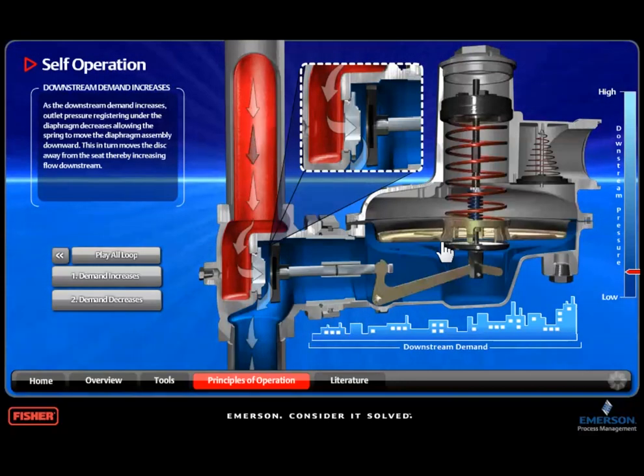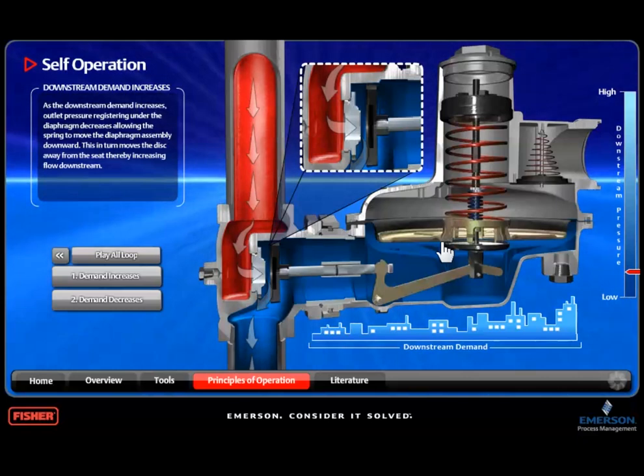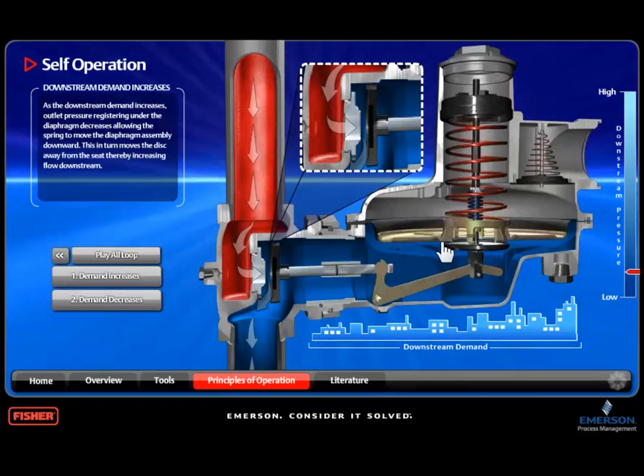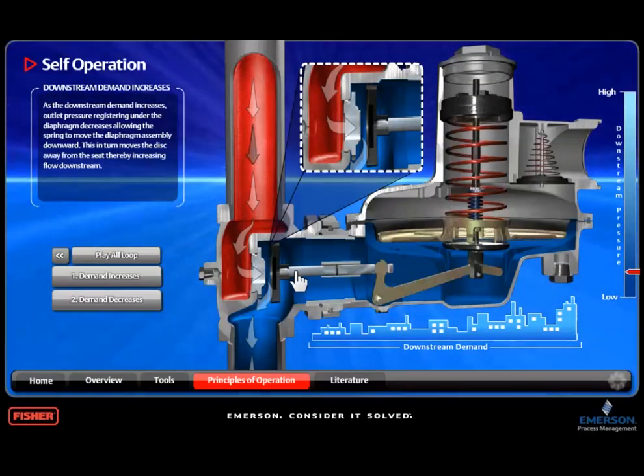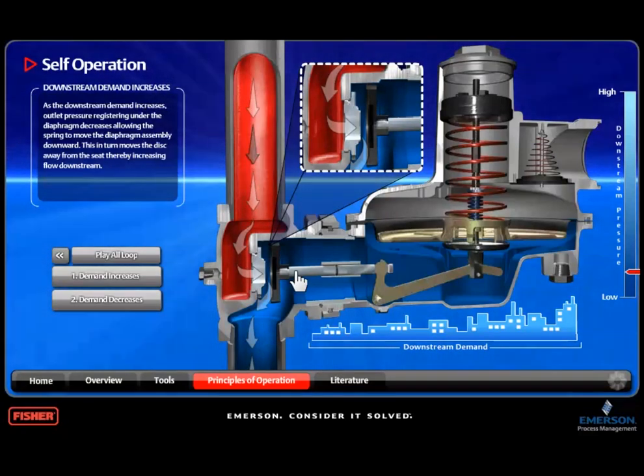This isn't a temporary decrease in outlet pressure. Outlet pressure will stay at its decreased value as long as the heater or other equipment is on. In order to meet the flow demand from the heater, the flow area created by the valve disc must be open a certain amount, and the only way the disc will stay in that position is if outlet pressure stays at the decreased value. We refer to this as droop.